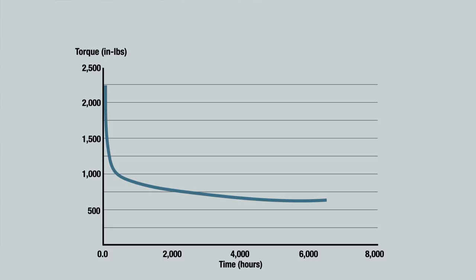The curve illustrates the load a gearbox can withstand over time based on the mechanical strength of its components. Be aware that the time range on the x-axis — zero to eight thousand hours — varies from manufacturer to manufacturer depending on their gearbox type and testing protocols. The life curve also gives us yield strength, which is the torque value where the components of the reducer will fail. This life curve is an example of a continuous duty life curve. There are no adjustments made to the reducer's life for other conditions such as side loading, which would affect the output bearings, or temperature, which would affect both lubrication and duty cycle.